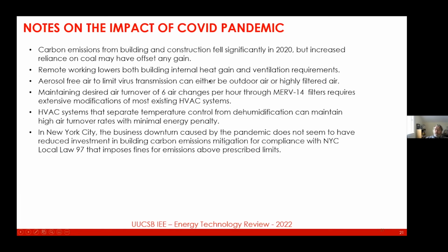Aerosol-free air to limit virus transmission can be either outdoor air or highly filtered air. And so the ASHRAE Epidemiological Task Force established some guidelines for air turnover and air delivery, and really stressed the importance of maintaining something like 6 air changes per hour through MERV 14. And to do that would require extensive modifications to most existing HVAC systems. However, HVAC systems that separate temperature control from dehumidification can maintain high air turnover rates with minimum energy inefficiency.